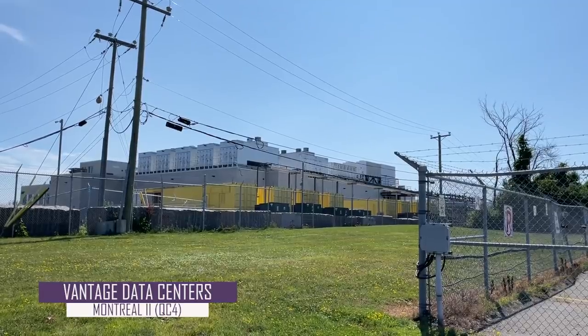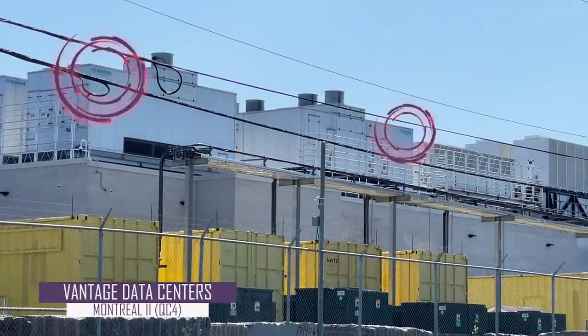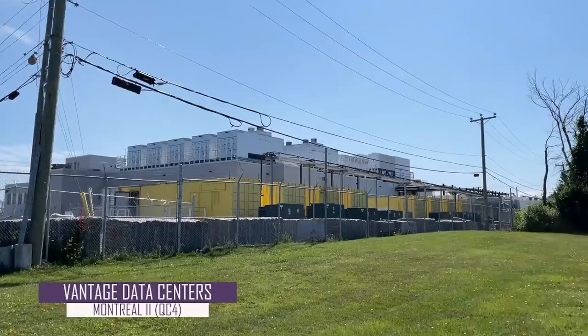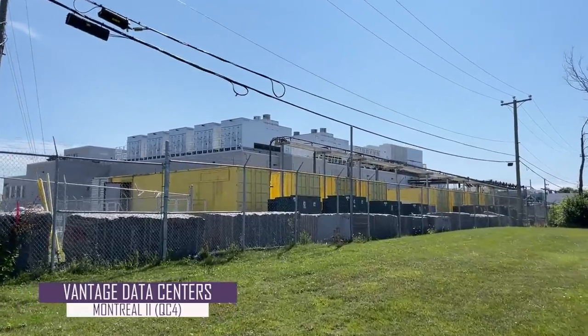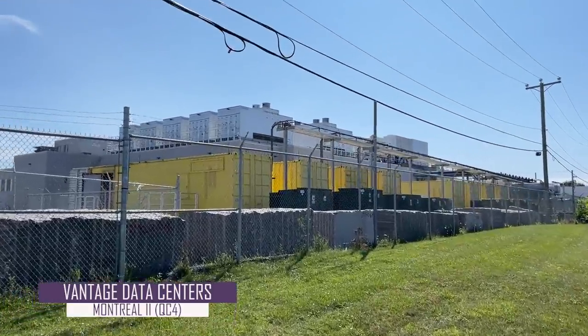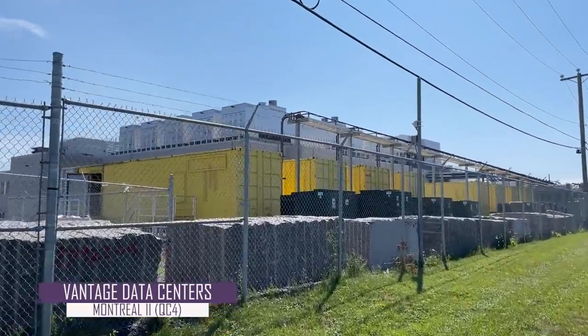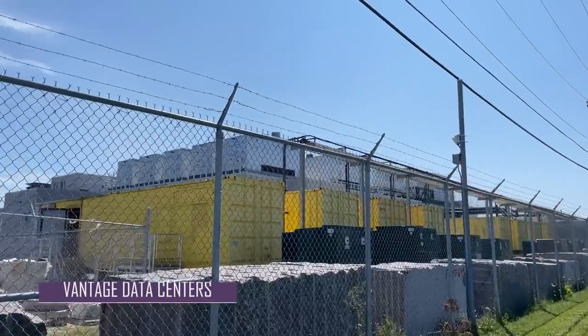Finally, you can see on screen these air handler units from Munters, which provide ventilation, filtration, and humidity control to prevent damage to the servers inside the data center from incorrect moisture levels.